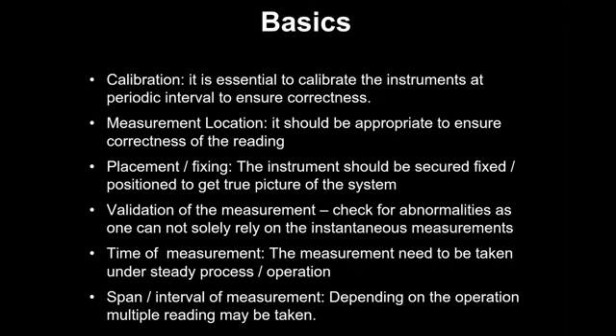Here we were doing an audit for a power plant flue gas analysis. So for flue gas analysis, we need to measure carbon monoxide, temperature, and oxygen content at different locations along the duct. So our team members went, and they tried to take the oxygen measurement.